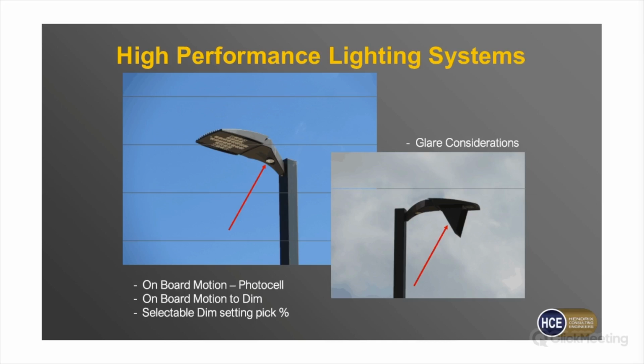One of the cool things is you can still run all these lights on one circuit and run them to a contactor, connect that contactor to your BMS, so you can control the schedule from your BMS or a time clock, either way. We used to run multiple circuits around the site, the ones close to the building as zone A, the ones away from the building as zone B.